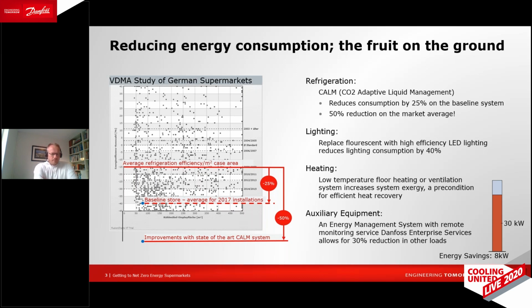In terms of heating, of course, it's important to insulate the store well. But what is also interesting is that we can reuse the energy from the refrigeration system, the condensing side. The best way to do that is if you have a low temperature heating system, so floor heating, or even a ventilation fan coil, where you make sure that you have a low return temperature on the hot water going back to the recovery system. This is really a precondition to have efficient heat recovery in a store.